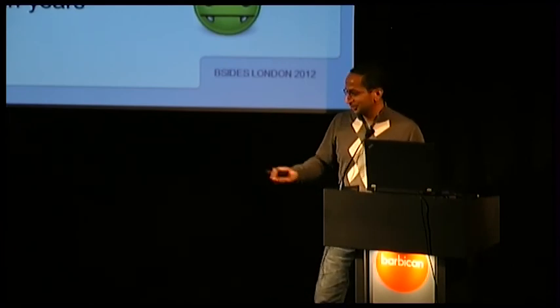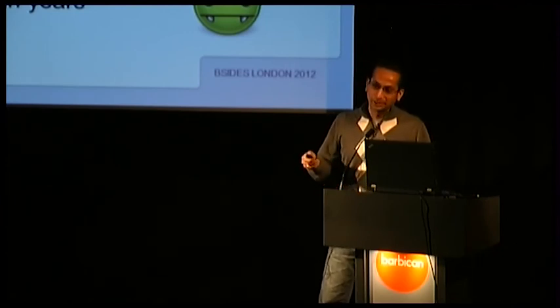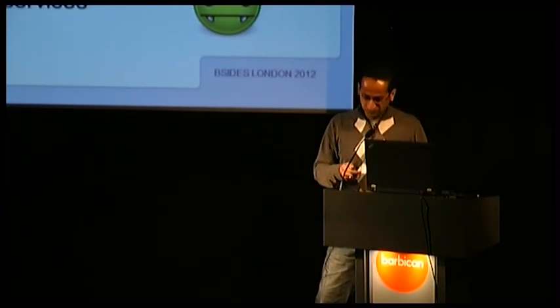There are systems that we saw that were not restarted in years. And when we asked why have you not restarted this system in years, the simple answer that we got was that they were not sure that the system would come back up again if they restarted it. And this is your critical infrastructure system. Even I chuckled at the time, but it is a fact. We saw a couple of systems running Windows NT, Windows 2000, and systems which are actually obsolete and for which patches are no longer available.